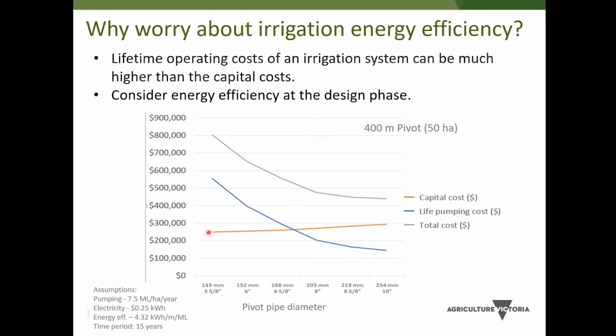The capital costs shown in orange here range from about $250,000 up to almost $300,000. But we can see the lifetime pumping costs of the under-designed system are much higher, almost double the capital costs. Whereas if we design the system well, the pumping costs are much less than the capital costs of the system. So the grey line's the total cost of owning the system. Really important that we do get that design right.